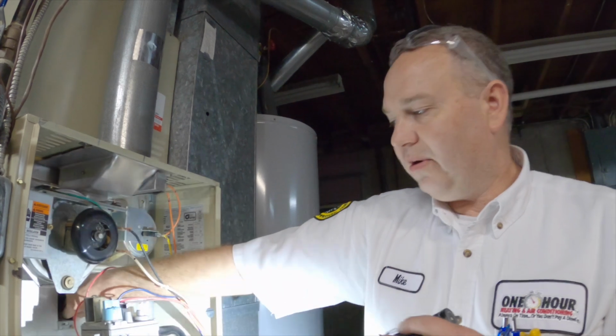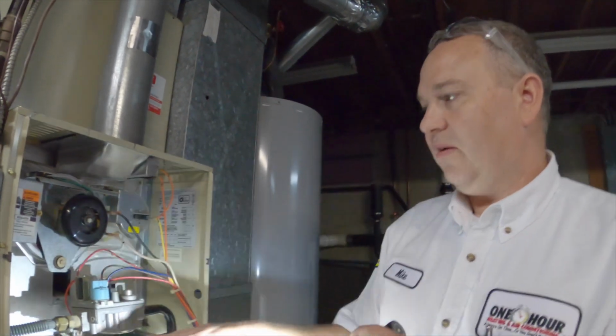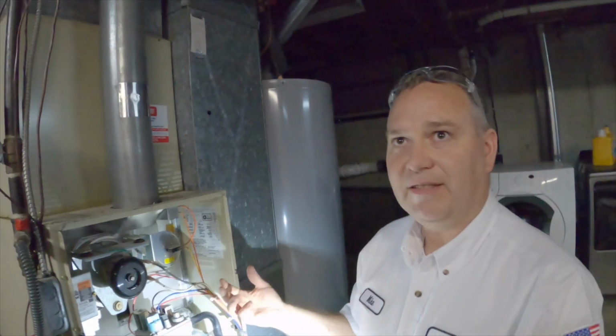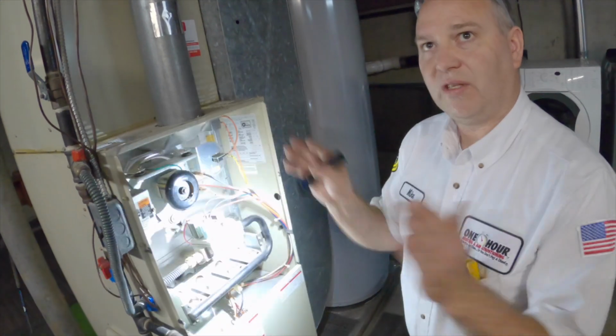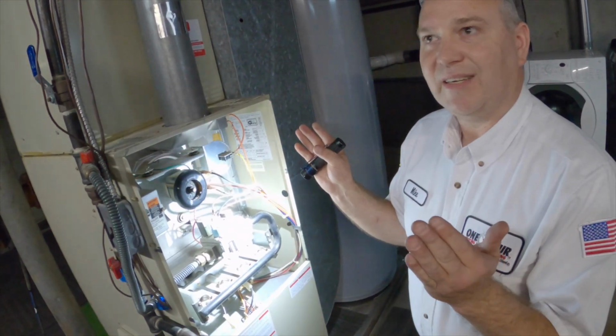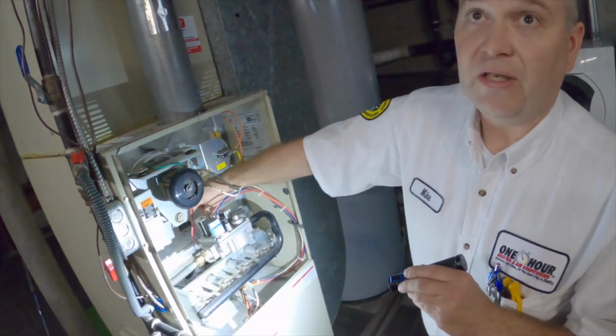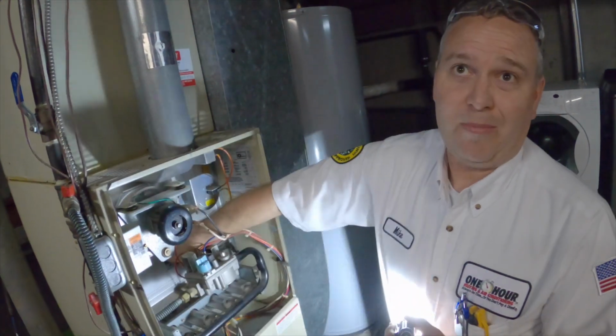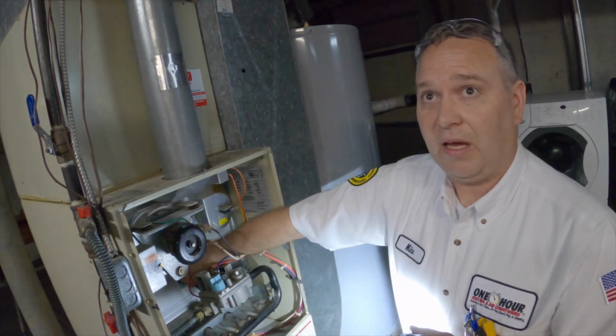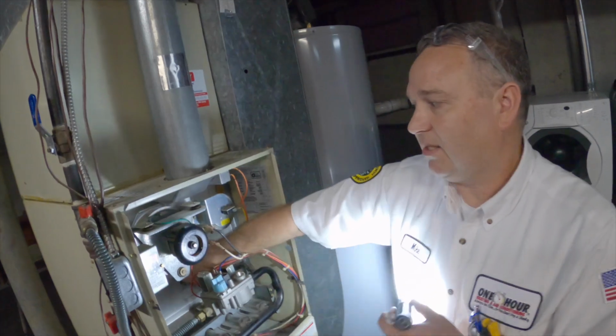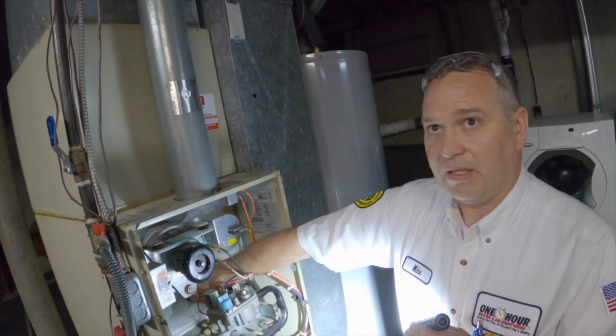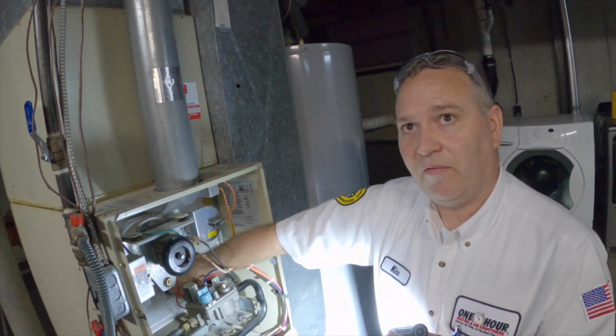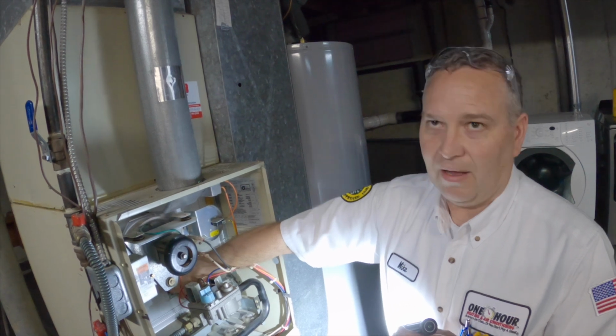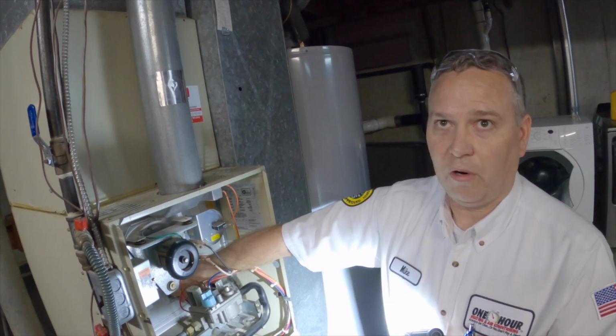The hottest part of the furnace is right there where those burners go in, and that dimple — every time this furnace comes on and shuts off, it expands and contracts. Eventually, it's like bending a paperclip back and forth — the heat and the bending back and forth breaks it. That's essentially what's happening. This furnace is notorious for that, and I can reach my fingers in the limit hole and actually feel the crack.